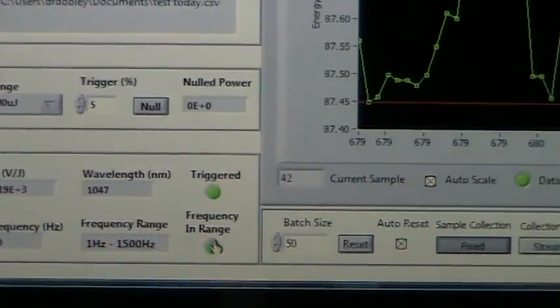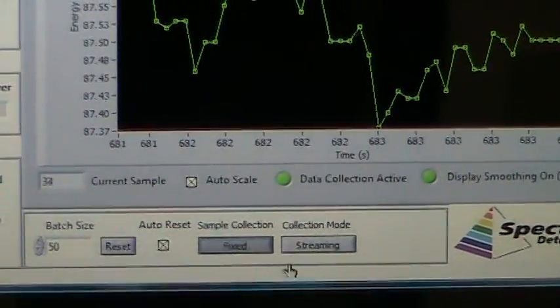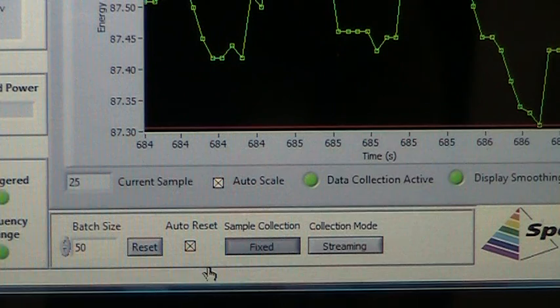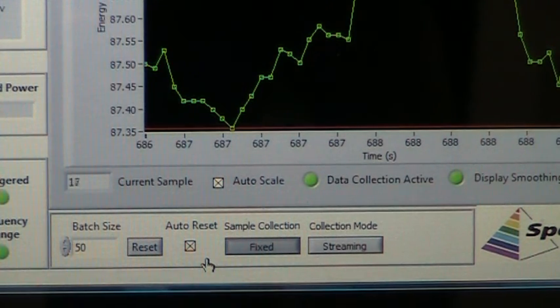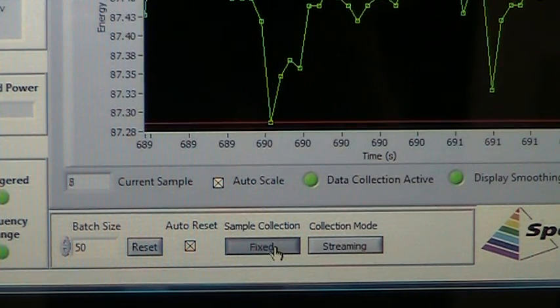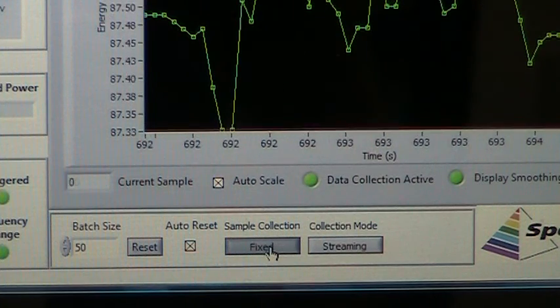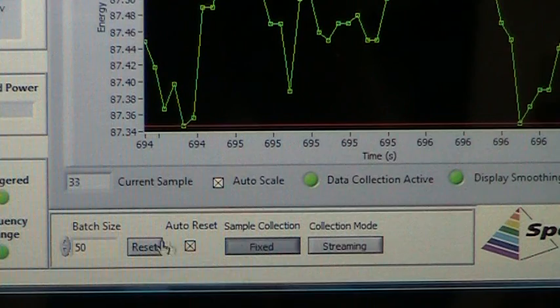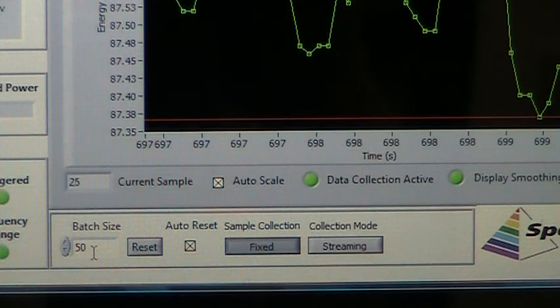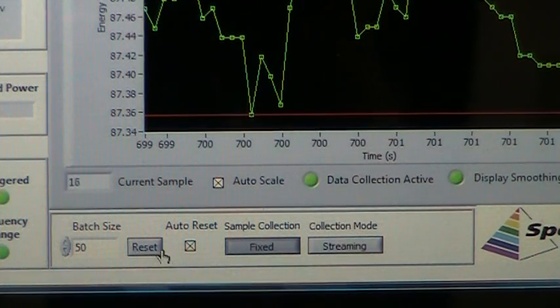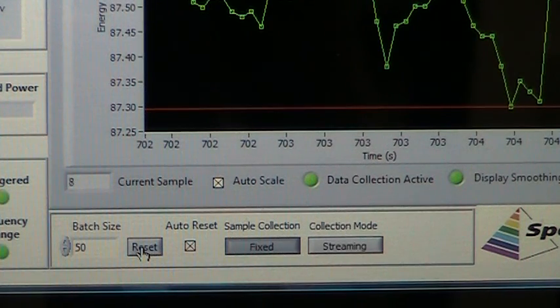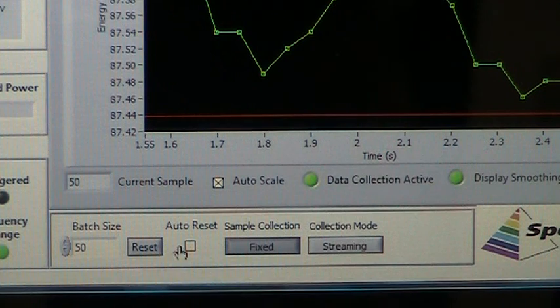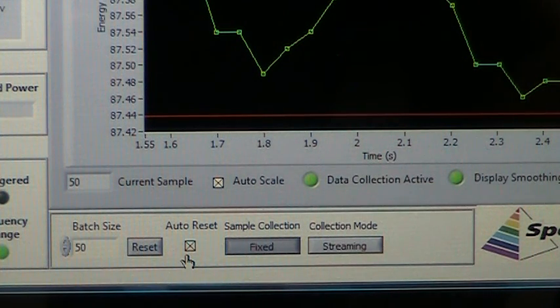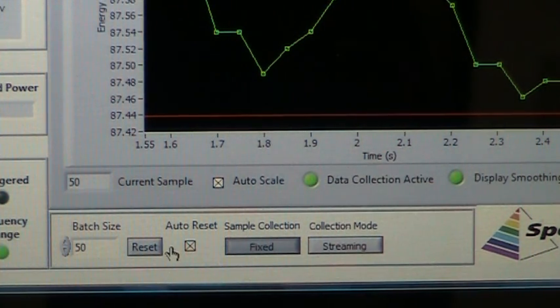Now let's move to the right underneath the strip chart. This is where the user will set the method of collecting data. In this window here, it's called sample collection, you can set fixed or continuous. In the fixed mode, you're actually going to set a batch size. We've set a batch size of 50. You can reset that manually or use auto reset. Right now we're in the auto reset mode, so it will update every time it gets 50 pulses.